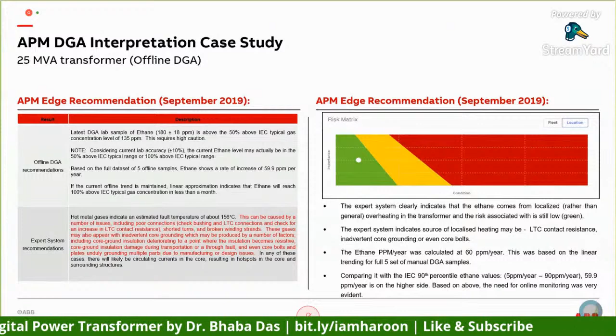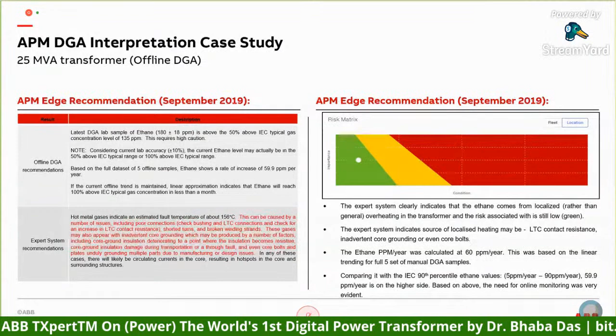So we put in an online DGA monitor to verify whether what the software said, that IEC ethane gas levels would go up within 1 month's time, is correct or not. We installed the online DGA device. And what you see here, I took the data from the online DGA device and did a linear fit of the values. You can see that from September 2019, it crossed 200 in mid October. So what the software predicted, that in 1 month's time you will cross, actually crossed.